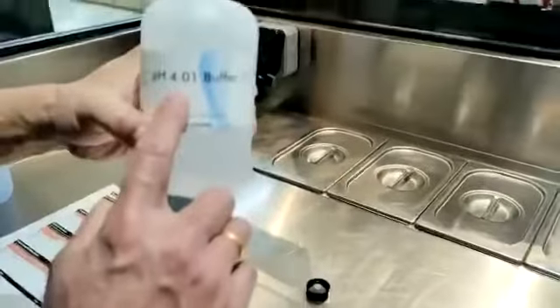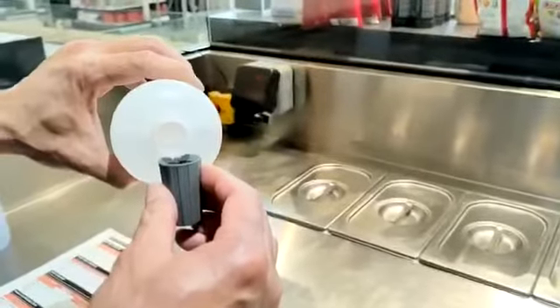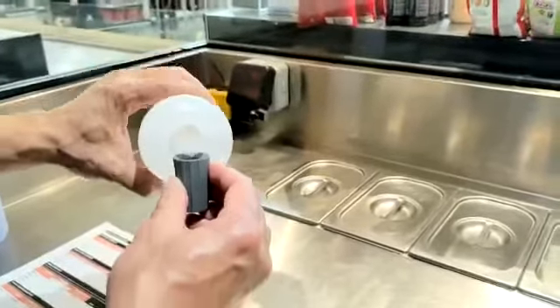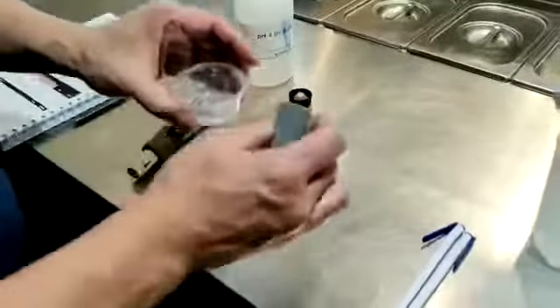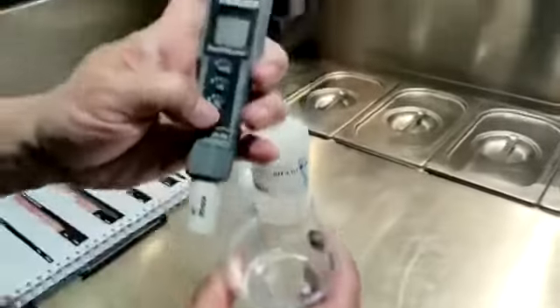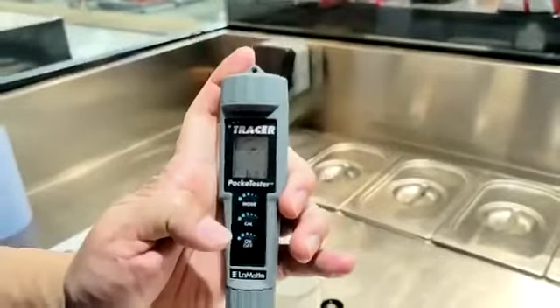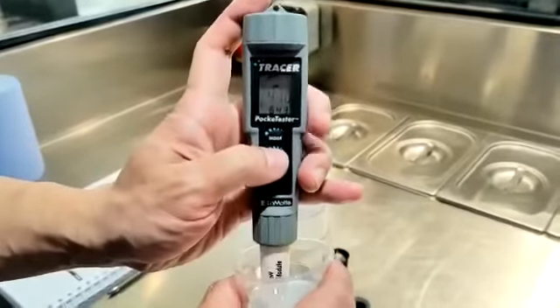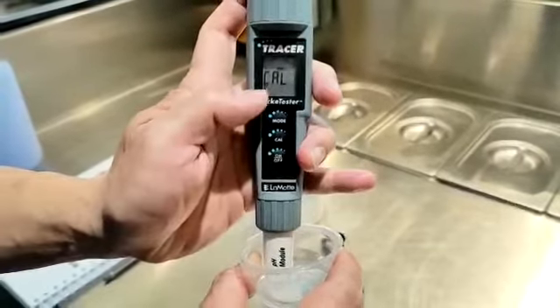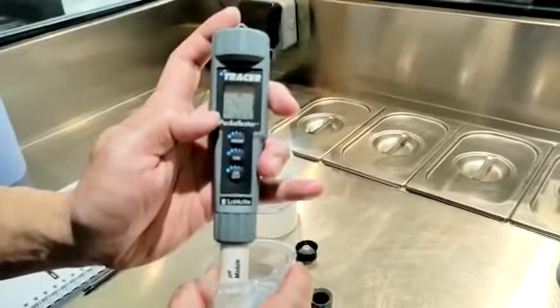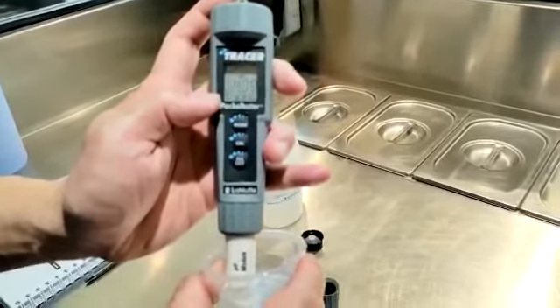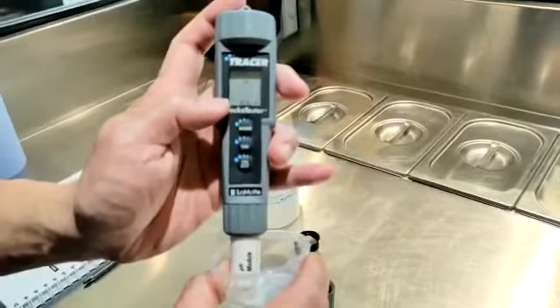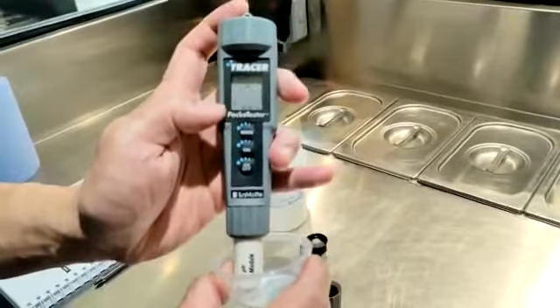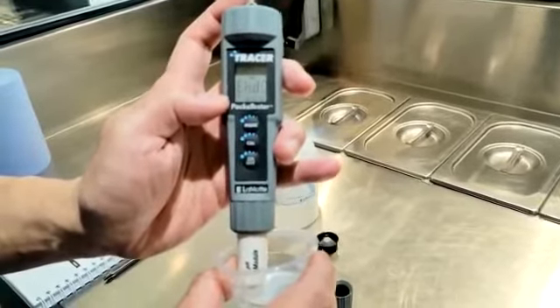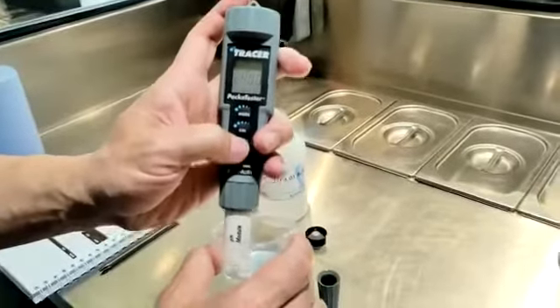This is the pH meter we normally use, and we use a pH 4.01 buffer solution. We take a little bit of the buffer solution here, and then we turn it on, dip it, and press CAL. Press for 2 seconds and you see CAL on the screen. Now it's still flashing. The number has to be 4.00. Now 4.00, and wait until you can see M on the screen. M, done. So the calibration is done. We just turn it off.